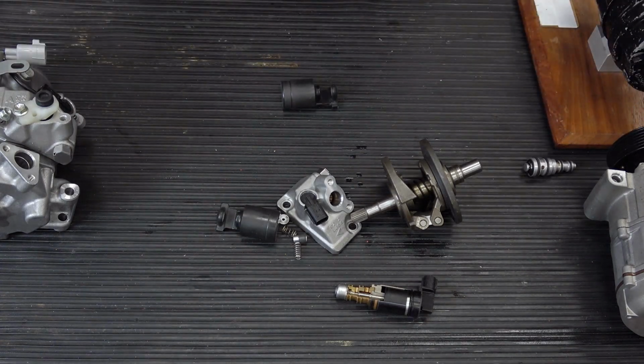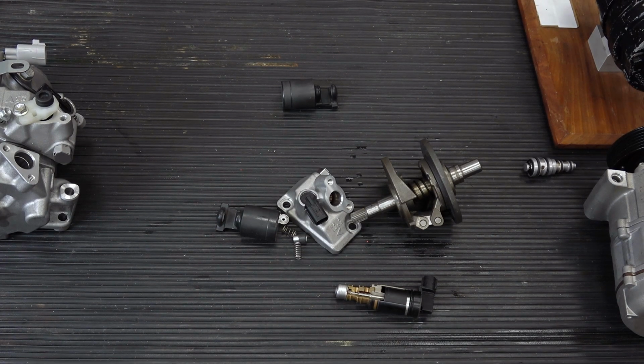So let's go back to our presentation here for just a minute, and we'll go right on from there. So now let's talk about how original compressors fail. I'm going to make this pretty quick. PAG oil and R134a mix together well when they're both liquid. But inside the evaporator, when the refrigerant evaporates, there's a very weak molecular bond between the R134a and the PAG oil. And so as the refrigerant evaporates, it tends to leave the oil behind.